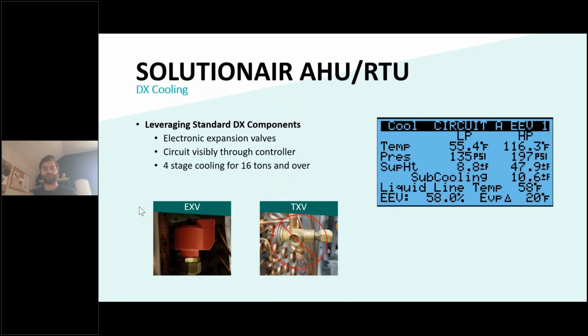Additionally, we've standardized around EX valves instead of TX valves. Just allows all the information from that refrigeration circuit to be brought up on our controller. We also do have options of sending in remote modem controllers so that we can tie into those controllers, and our tech support from Winnipeg is able to view that refrigeration circuit and try and identify any issues within it remotely. So that's another great bonus for us.